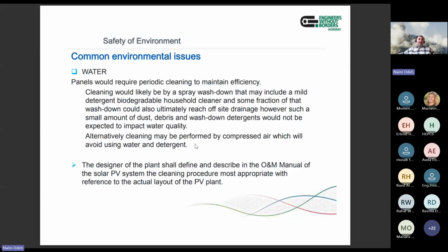The other point is about water. Here we mean two things: using water for cleaning, which consumes a lot, and it is highly recommended to save water as much as possible. To decrease water usage in cleaning, it is recommended not to apply wet cleaning all the time. You can try dry cleaning for the solar modules, which is also recommended and used. I personally applied this with previous colleagues in the Middle East, and it works to go with dry cleaning, applying wet cleaning only maybe 4 times a year, and the rest of the time doing dry cleaning regularly, every 2 weeks or every month. There are a lot of tools that can do dry cleaning.